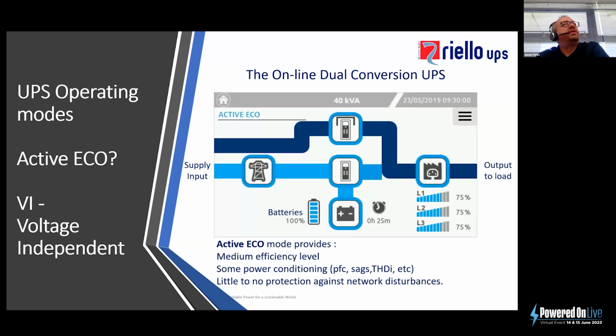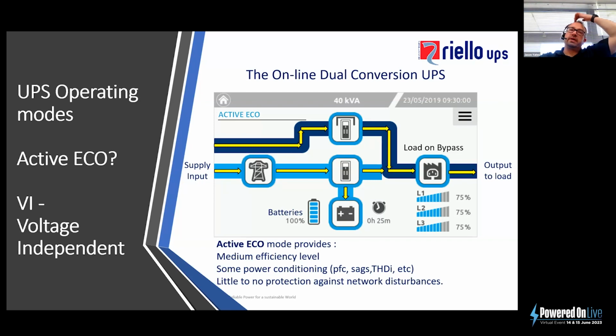The next mode of operation is sort of like a mixture between the eco mode and the online mode. This is referred to in our case as active eco. Some manufacturers will call them dynamic eco, various different names. They'll all give them different names. But basically, it's very similar to the eco mode in that the load is being provided through the bypass line, so we've got a good high efficiency. However, this time, the actual UPS system inverter is working in parallel with the bypass line.